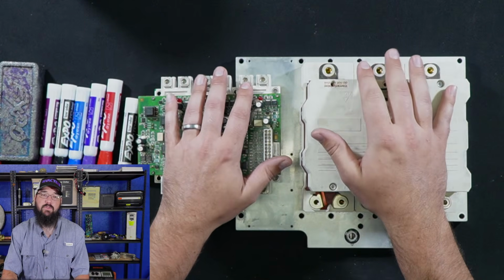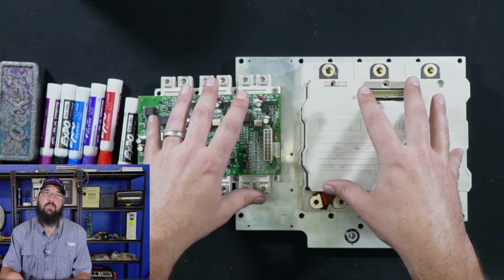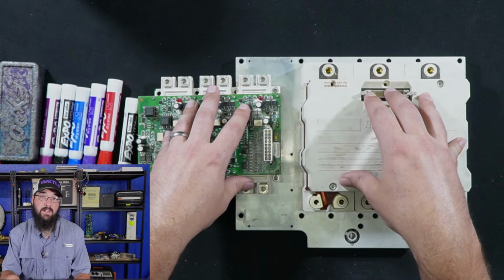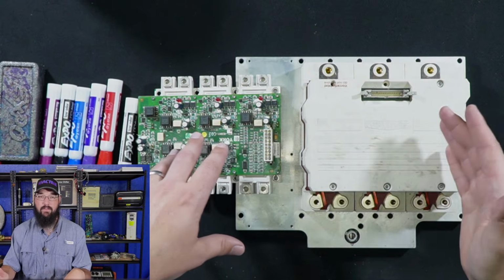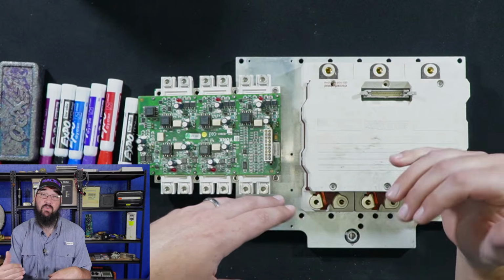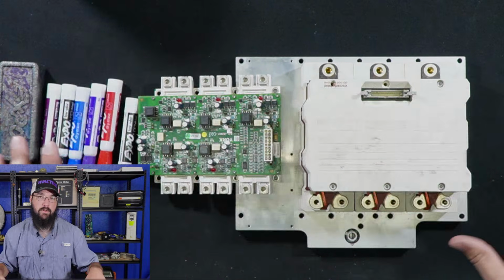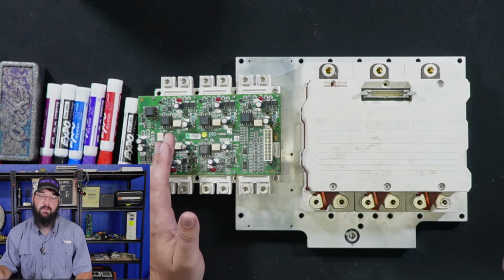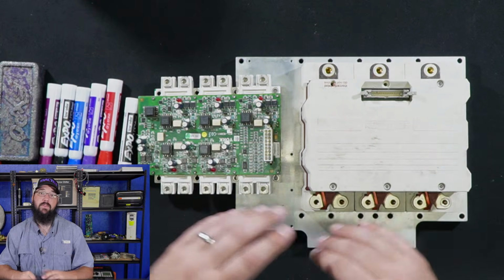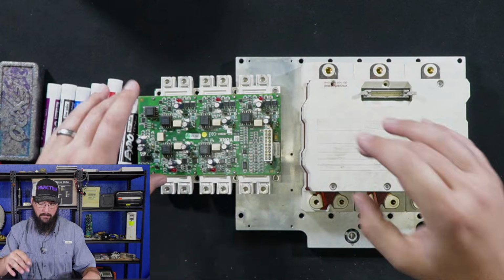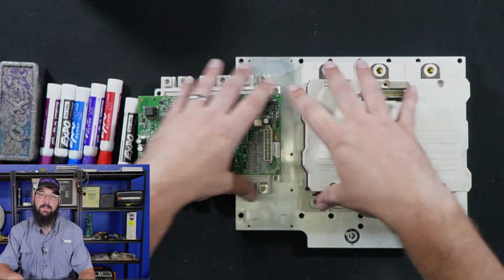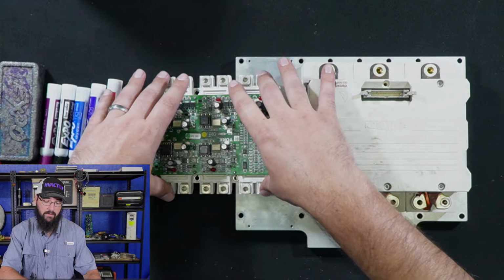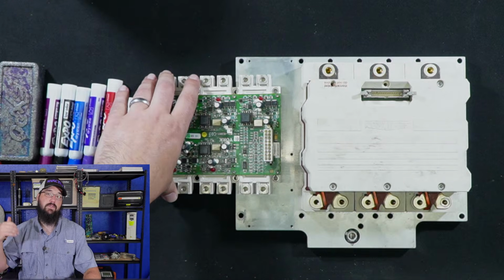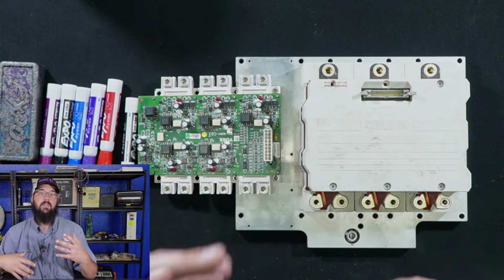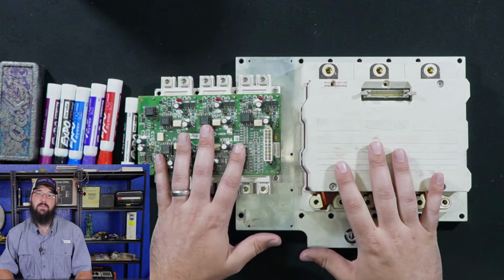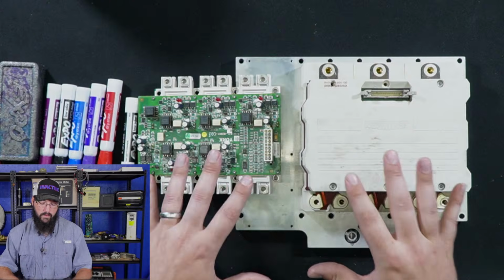These are some of the tests we should do in order to verify, hey, is this even safe to turn on, right? So if we are having an overcurrent fault, especially as soon as it goes to turn on, or if we have fuses blown, period, before we go any further trying to put new fuses in or reset things, we want to get in here and make sure that these types of modules, this is true for the IGBTs or the inverters, true for the rectifiers or the SCRs, we will have to verify this whole circuit before we try to put power back to it, because these components will literally explode on you.